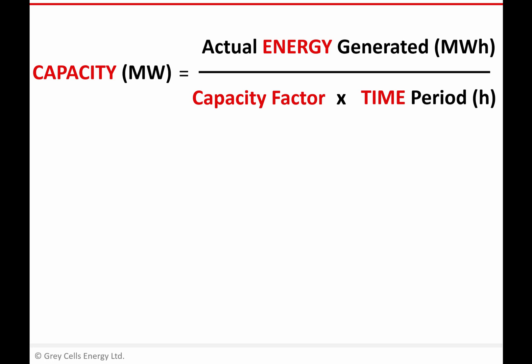And obviously, if energy is the same in both cases, but capacity factor is lower for solar than for coal, for example, you'll need to build a higher capacity of solar to replace a certain capacity of coal. You'll need to build more megawatts to produce the same number of megawatt hours if the capacity factor is lower.